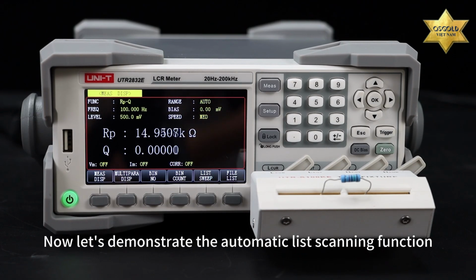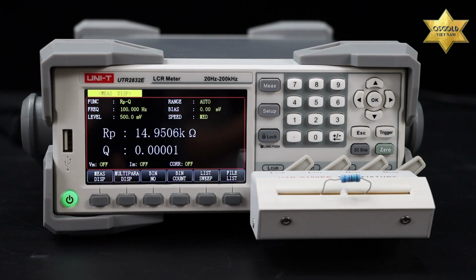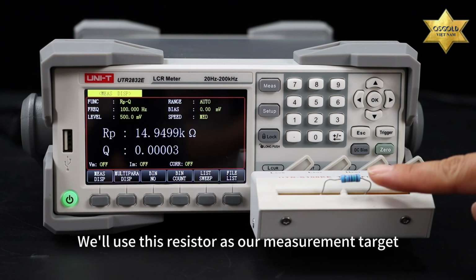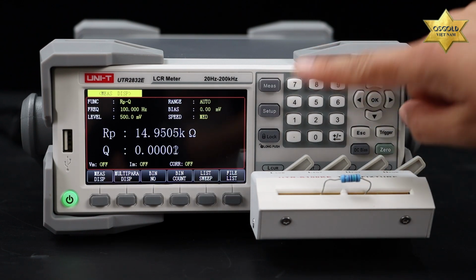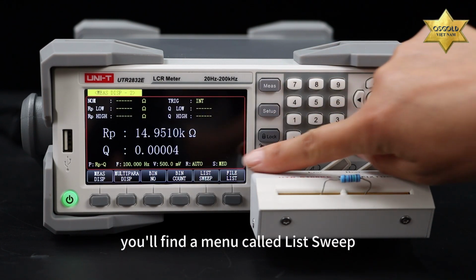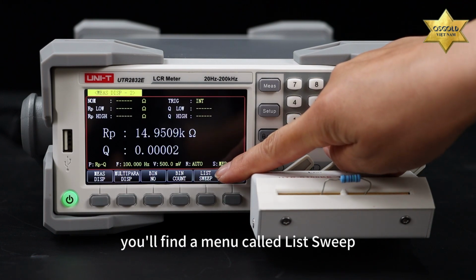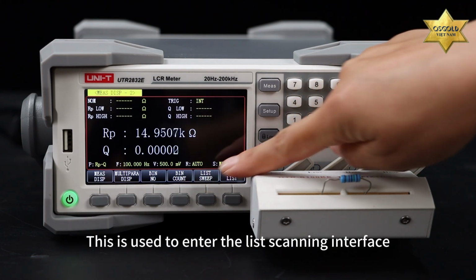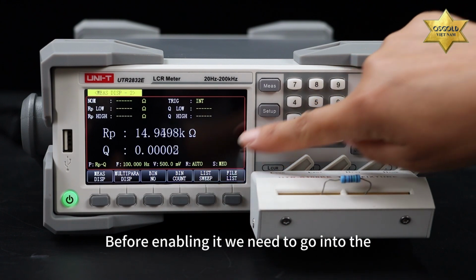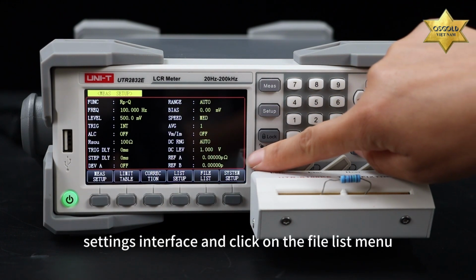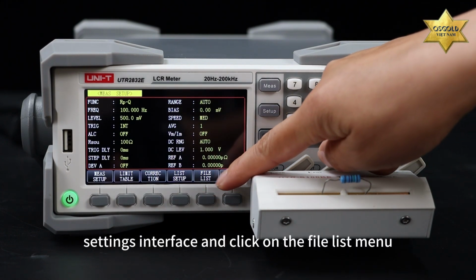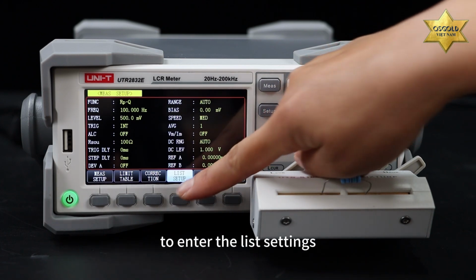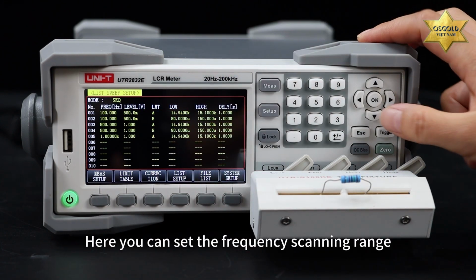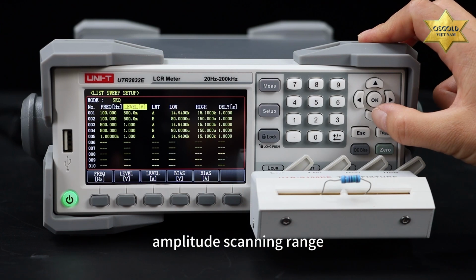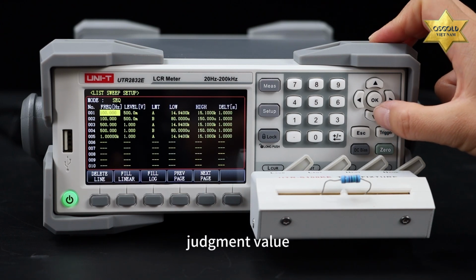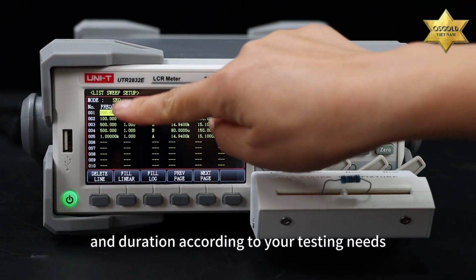Now let's demonstrate the automatic list scanning function. We'll use this resistor as our measurement target. In the measurement interface, you'll find a menu called List Sweep. This is used to enter the list scanning interface. Before enabling it, we need to go into the Settings interface and click on the File List menu to enter the list settings. Here, you can set the frequency scanning range, amplitude scanning range, judgment value, and duration according to your testing needs.